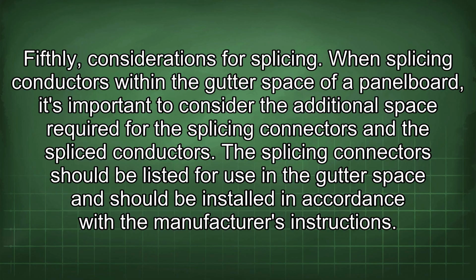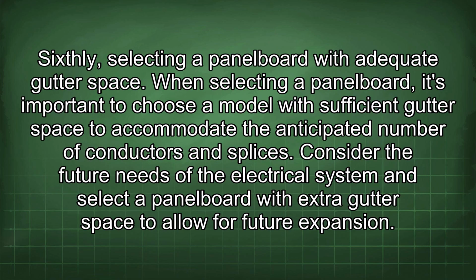Fifthly, considerations for splicing. When splicing conductors within the gutter space of a panel board, it's important to consider the additional space required for the splicing connectors and the spliced conductors. The splicing connectors should be listed for use in the gutter space and should be installed in accordance with the manufacturer's instructions.